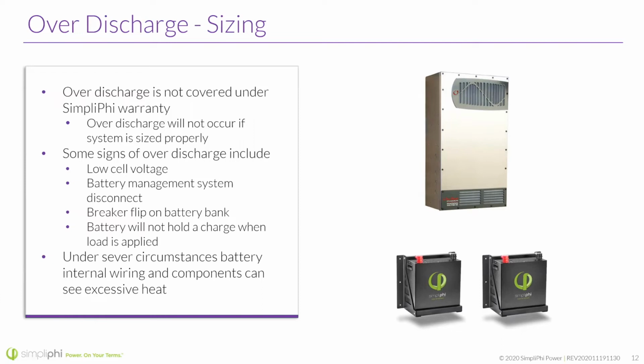That could be a sign of over discharge. That does not mean that breaker actually flips. That just means that the battery has gone into an open circuit internally. Typical signs of this will be extremely low voltage on the battery. Again, that could be a sign of protection, but it also could mean that the over discharge occurred already.